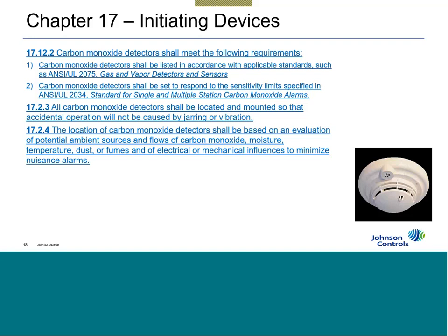I have seen some duct carbon monoxide devices on the market. And I get calls on this saying, Roger, am I allowed to do this? Code does not address carbon monoxide duct detectors because there is no UL listing for it, there is no standard for it, there has been no testing for that. So any of those that are out there that are in use are strictly for environmental use, meaning I see a certain part per million, I turn fans on, maybe alert the HVAC system or something of the like. But they are not suitable, listed, or to be used for fire alarm life safety use.